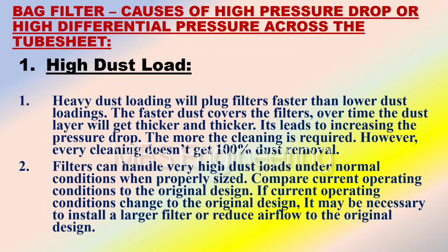Point number 2. Filters can handle very high dust loads under normal conditions when properly sized. Compare current operating conditions to the original design. If current operating conditions have changed from the original design, it may be necessary to install a larger filter or reduce airflow to the original design.